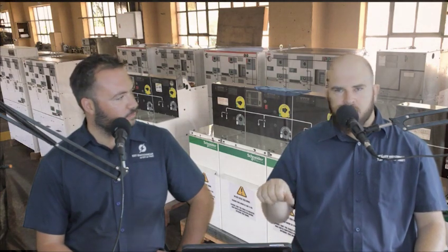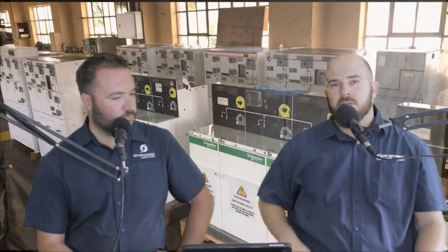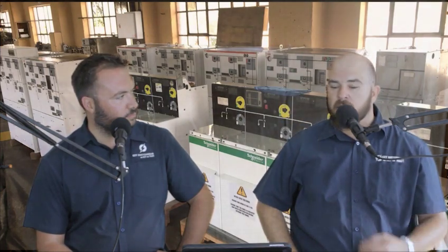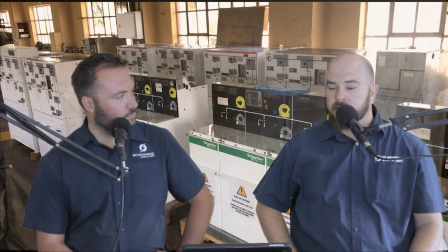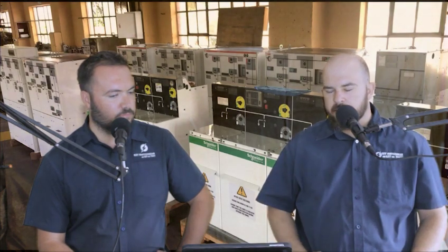An isolator, on the other hand, is more like a light switch. You can switch it on, you can switch it off, but even if the house burned down, that switch cannot change position. So it cannot open or close on its own. That is an isolator or a disconnector. Both of them interrupt the flow of current, both of them isolate your voltage, but only one of them can actually break fault current, and that is your circuit breaker.